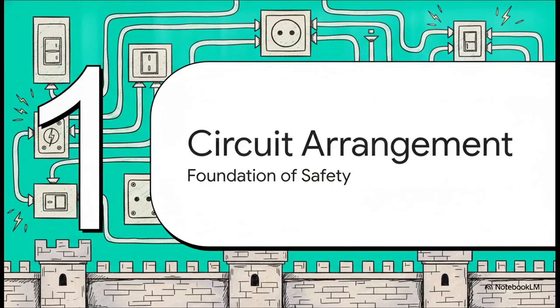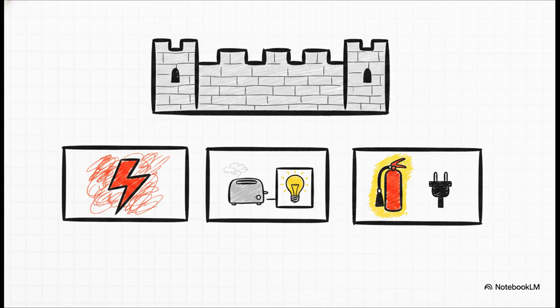All right, part 1, arranging the electrical installation. The standard explicitly states that an electrical installation has to be systematically divided into separate circuits. But why do we do that? Well, it's really all about containment and resilience. Think of it as the foundation of your fortress. First, we divide circuits to avoid danger during a fault. If one part of the system has a catastrophic failure, we want to contain that damage locally, right?